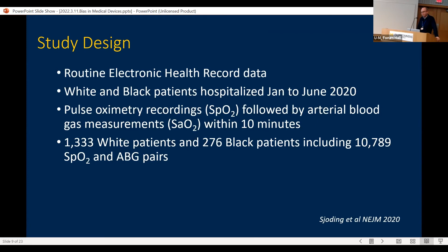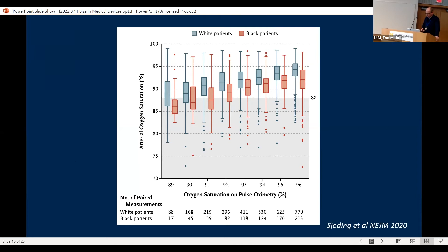And so, just using University of Michigan data, looking at patients who were self-reported as white or Black, hospitalized between January and June of 2020, we were able to get pulse oximeter readings followed by arterial blood gas results on over 1,000 white patients, over 250 Black patients, and 10,000 total samples. And when we analyzed this data, we saw that there was a clear discrepancy. Here on the x-axis is what the pulse oximeter is reading. When the pulse oximeter is reading 92%, a saturation we tend to think is going to be okay, the true arterial oxygen saturation in Black patients was actually meaningfully lower than in white patients, in a way that likely could be problematic in terms of the care that they're provided.